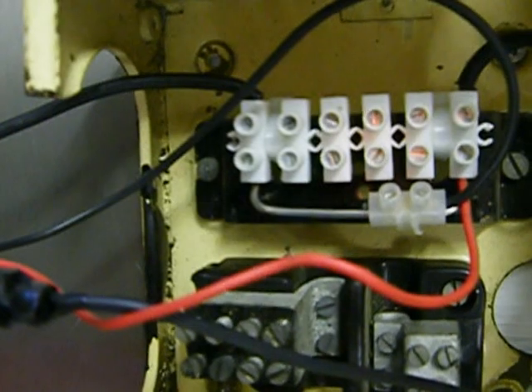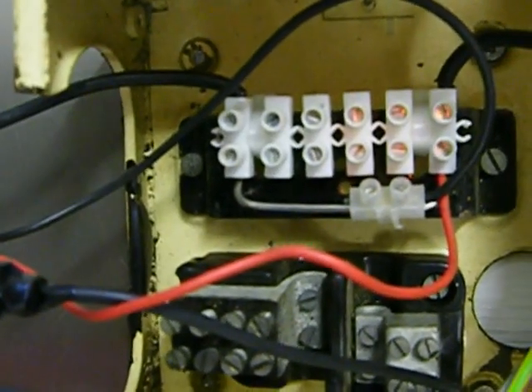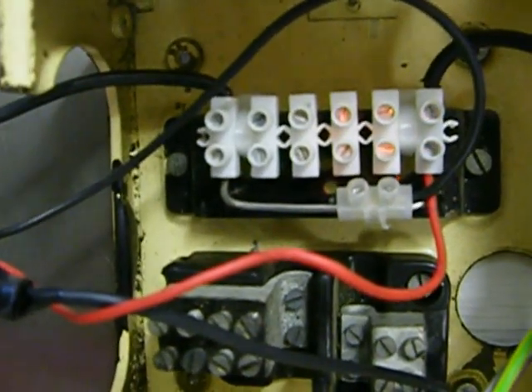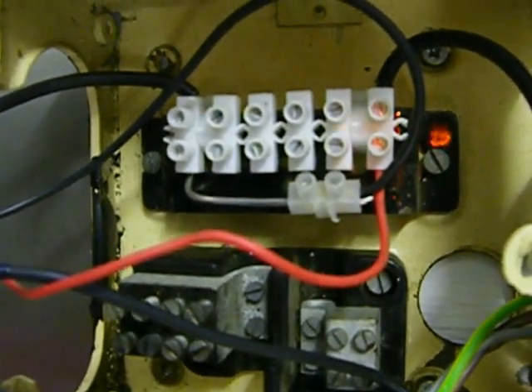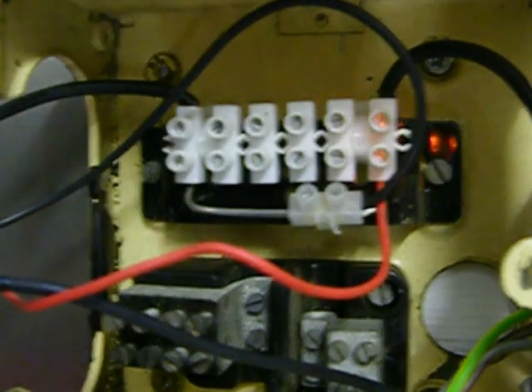I've put a piece of 316 stainless steel wire across the power feed to one phase of a three-phase motor. And then I've slid a wire to my millivolt meter up and down it until I get the right resistance. So the stainless steel wire is acting as a shunt.